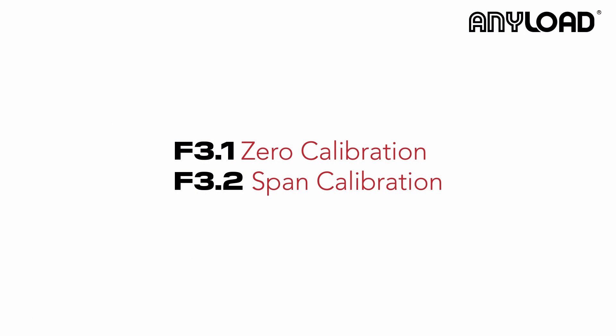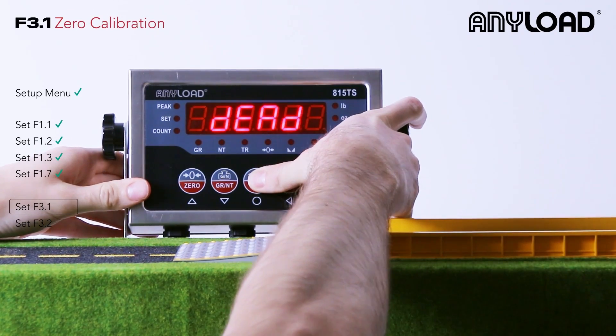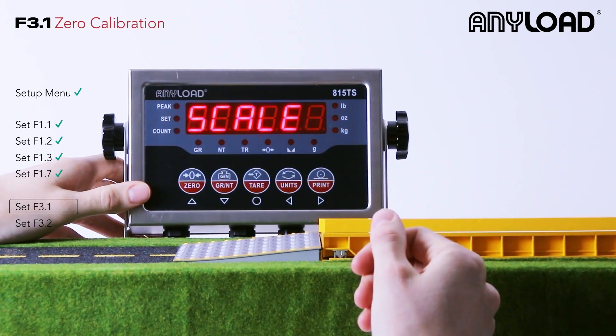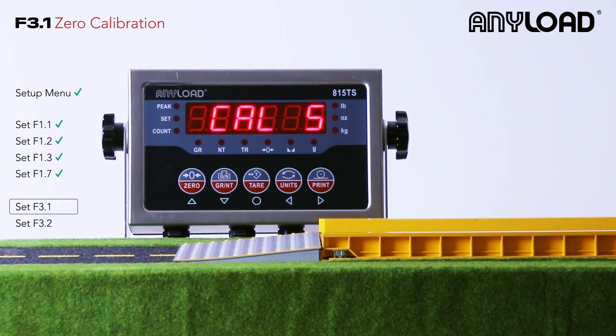Now we're going to get into our F3 settings, which include zero calibration and span calibration. Let's navigate to F3.1 and zero our scale. We're going to remove any weight from the scale. Once that's complete, press tare and it's going to start our calibration countdown.